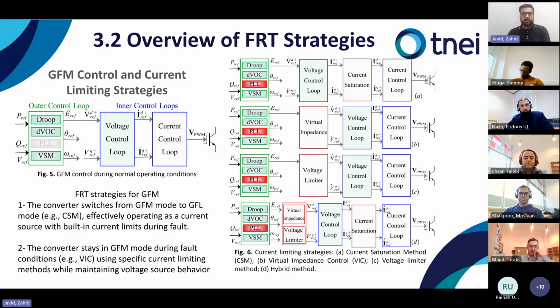The existing literature identifies two classifications of the FRT strategy. The first is where the converter switches from GFM to GFL mode. It will operate as a current source during the fault, and it will apply the current saturation method, like in the GFL, to limit the current. The second is where the converter stays in GFM mode like a voltage source, and we can apply virtual impedance control as a current limiting strategy while maintaining the voltage source behavior. This was just the overview, and there are also some hybrid methods that use a voltage limiter and virtual impedance, and then the current saturation method between the voltage and current loop. So there are different kinds of strategies available in the literature.